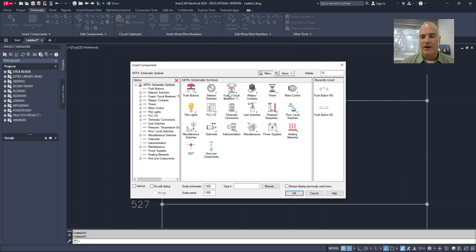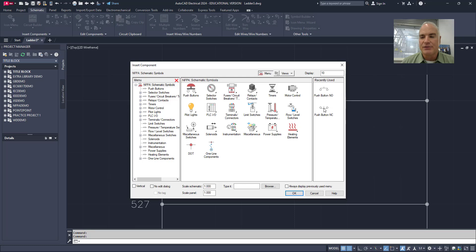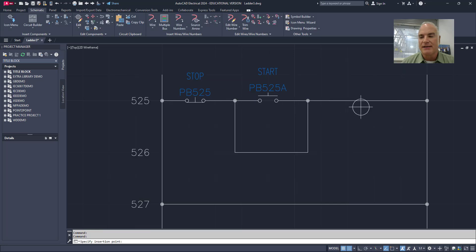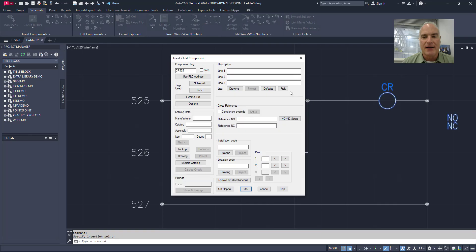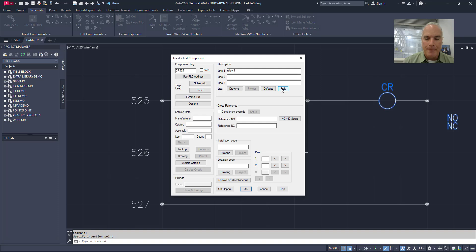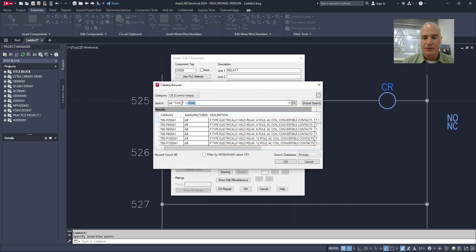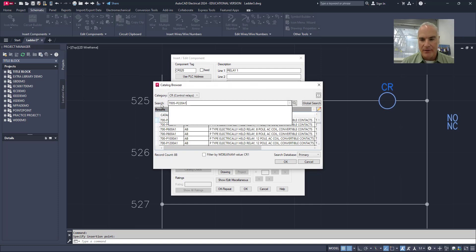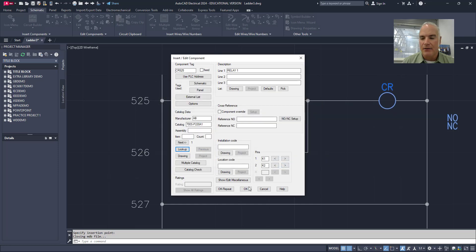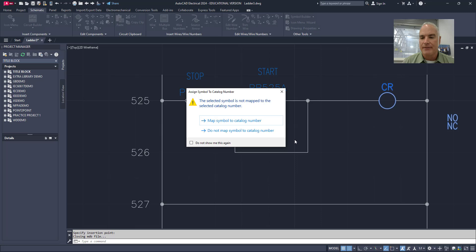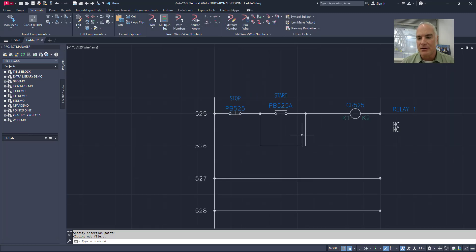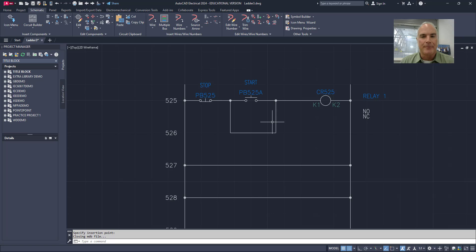So now going back to AutoCAD again, I'm going to go to the icon menu. And this time I'm going to go to relays and contacts. Notice, by the way, that recently used objects are over here. So that if I need to use them again, I don't have to dive back down. I can pick them up off of this. So I'm going to say relays and contacts. The relay that I want is this one. Outputs always go on the right side. So I'm going to put it over here on the right side. And this I'm just going to call it relay number one. Again, I'll go to look up and I'm going to paste that number in there. Enter. And that's the one that I want. Say OK. And OK. Again, map to the catalog so we're good to go. I've got my first row done.